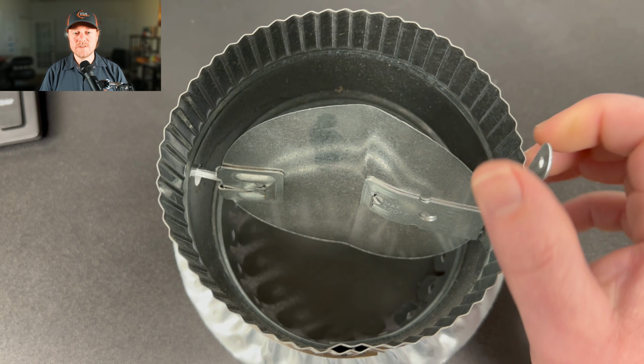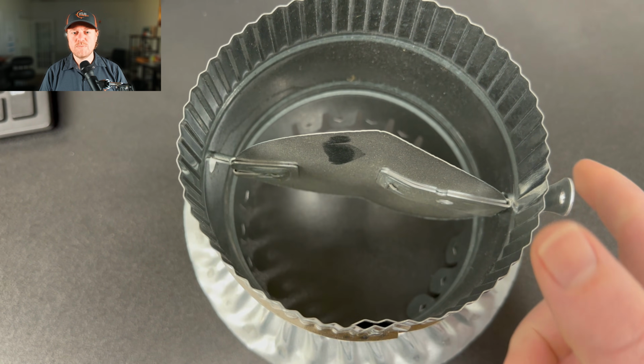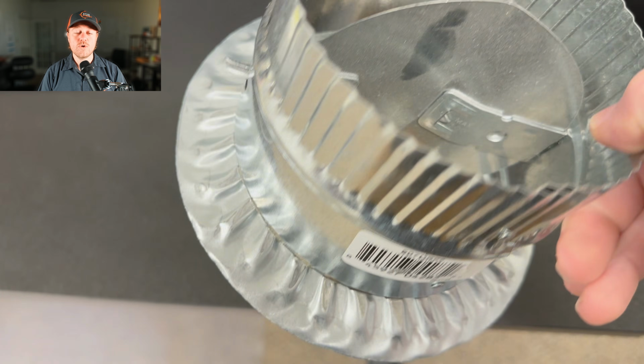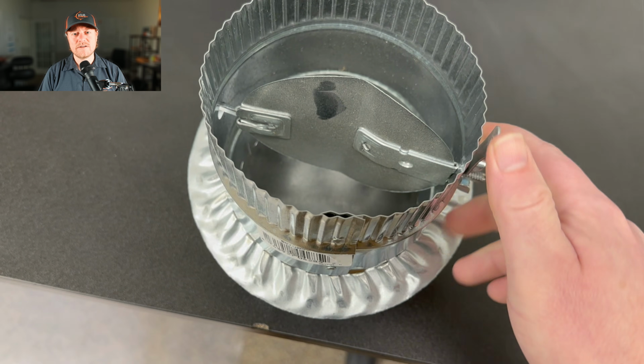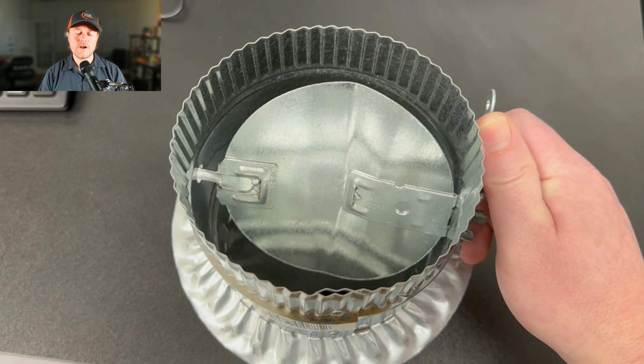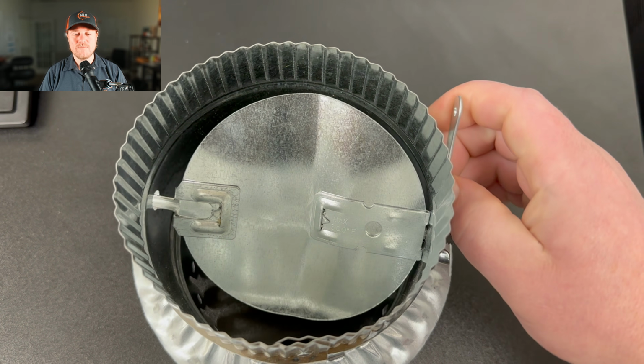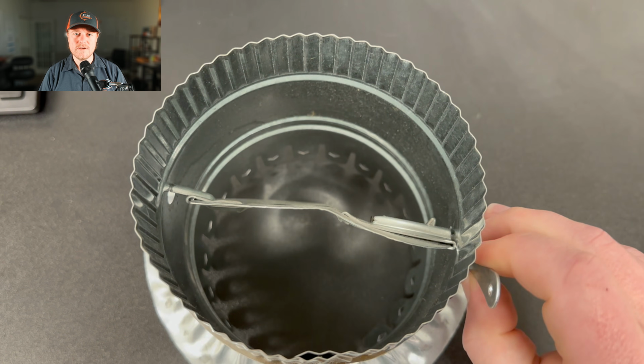An easy solution to solve this problem would be to use manual dampers to redirect airflow. I'm a really big fan of manual dampers because they're cheap, and it's a real easy solution to balance out airflow. If you ever end up making modifications to your ductwork, I'd always recommend making sure that manual dampers are included, for this one reason.